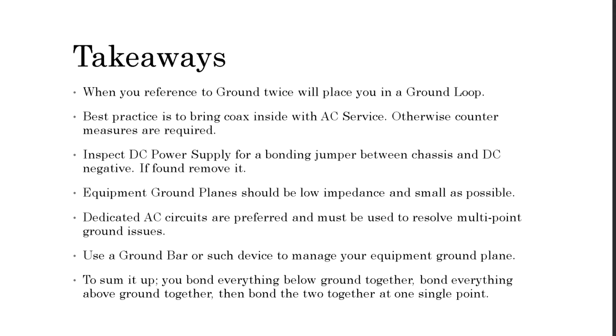Equipment ground planes, as we learned, should have a low impedance and be as small as possible. Dedicated AC circuits are preferred and must be used to resolve multi-point ground issues. Use a ground bar or such device to manage your equipment ground plane. And to sum it all up, you bond everything below ground together, you bond everything above ground together, then you bond the two together at a single point. And I think we're going to close with that.